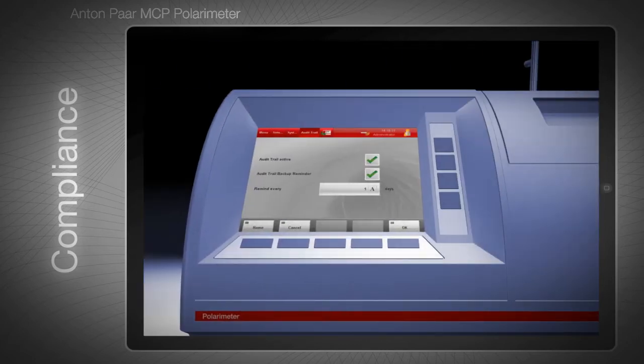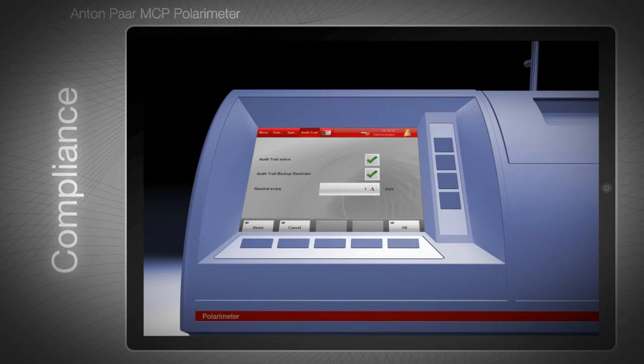The MCP's audit trail automatically stores all changes made to the instrument, including user changes, changes of accessories, and instrument checks and adjustments. As sample cells and quartz control plates are automatically identified by the wireless Toolmaster technology, the MCP's software records each time these accessories are changed, including date, time, user, and serial number of the cell or quartz plate. This provides an unsurpassed level of traceability in polarimetry.